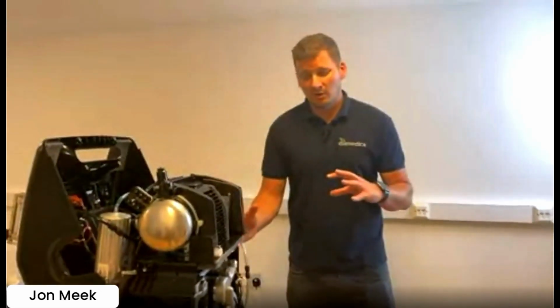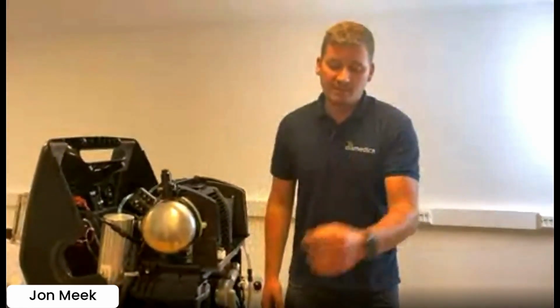Please take those questions. Okay, so the first one about the humidifier bottle. Inside the machine, it has a built-in fan, which maintains the temperature overall of the machine. Exactly like a car, it maintains it at 90 degrees. In here, the fan's designed to remove at full speed enough heat to maintain about 87 degrees inside. So we designed the flow rate to be controlled, as we tested the output of the warming of the bottle, to between 31 and 36 degrees. And again, that can change slightly depending on the ambient air temperature. But the temperature inside the machine is maintained by the fan, which keeps it at a steady temperature, which means we can actually use that to control the humidifier bottle.